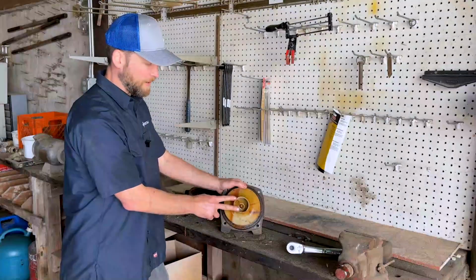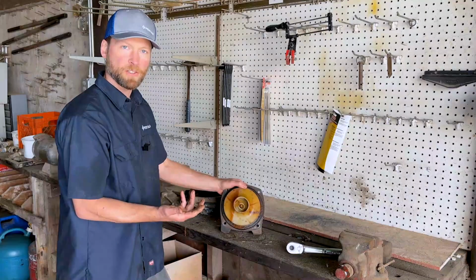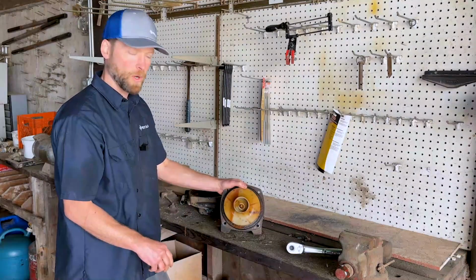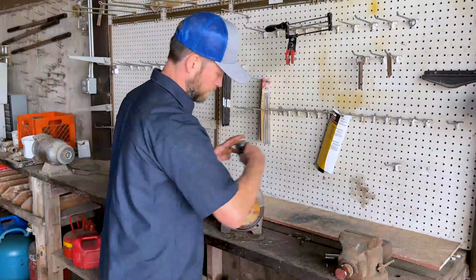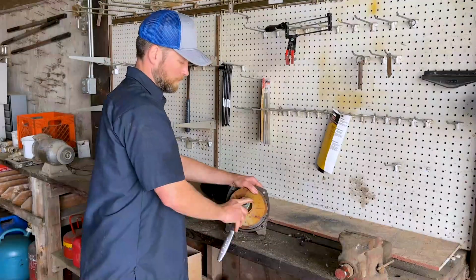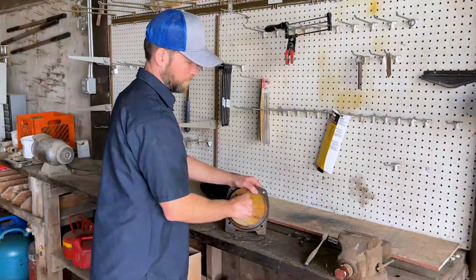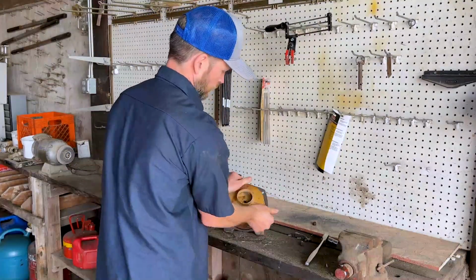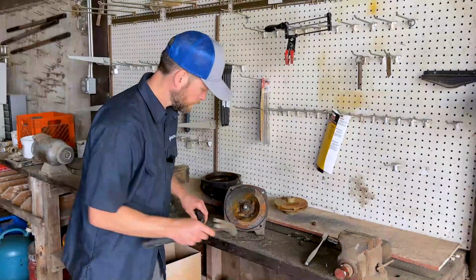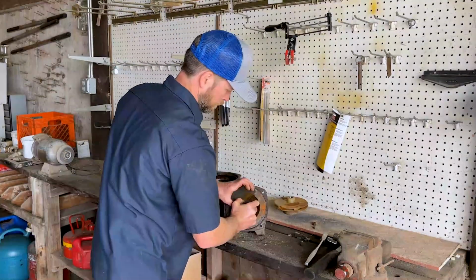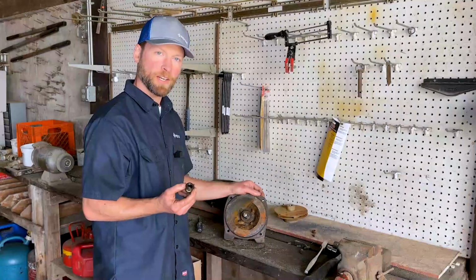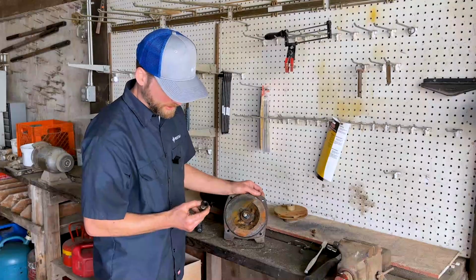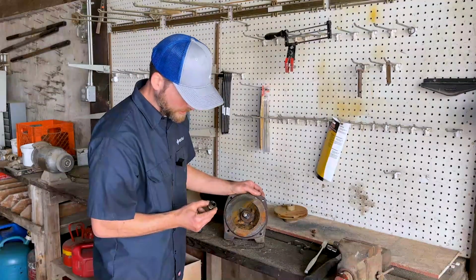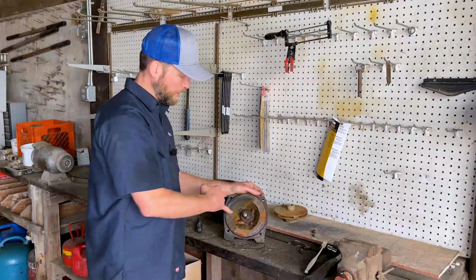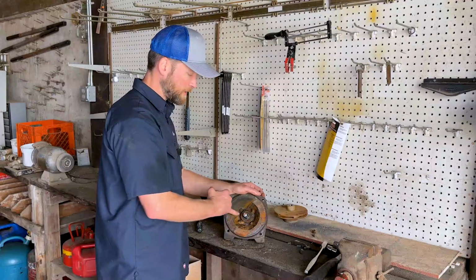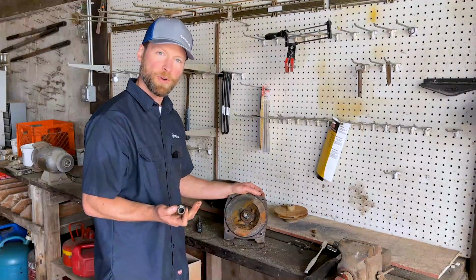So now I'm going to take off the impeller, and we'll take a look at the mechanical seal to see what that looks like as well. All right, now that I got the mechanical seal off, I am just taking a look at it. The seal faces do look like they're in pretty good shape. However, I noticed some discoloration on the shaft, which is most likely from a dry run event.